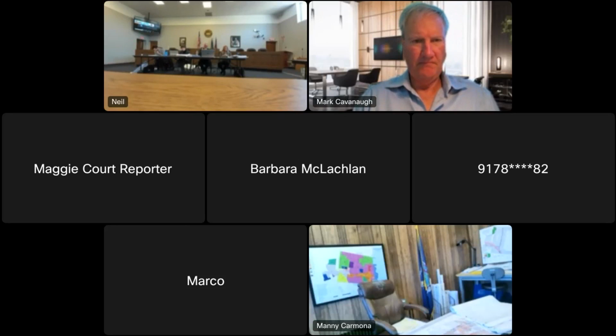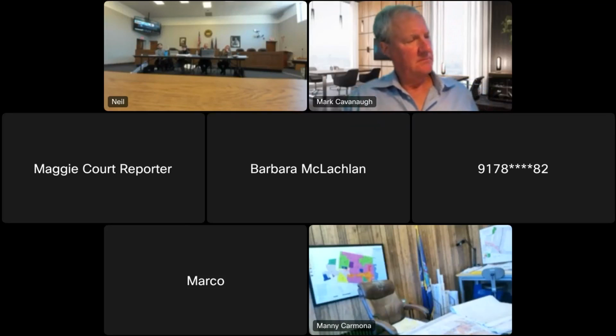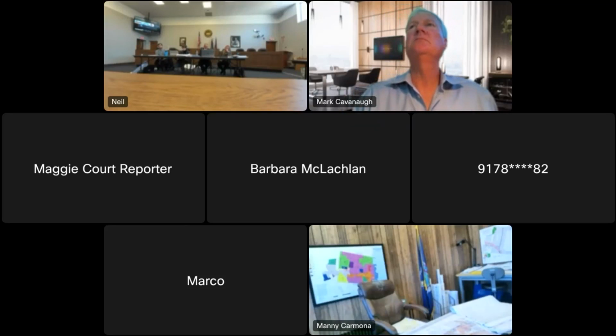Getting back to the water service coming into the buildings, can I tap off of that for the sprinkler system? For a 13D system, you can make the argument that you can do backflow provisions and tap off of there. For 13R, you cannot. But does the city have anything on this? Yes, it says you need a separate water tap.